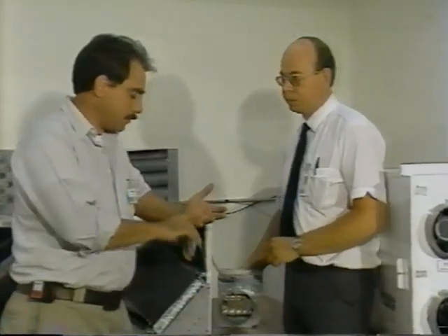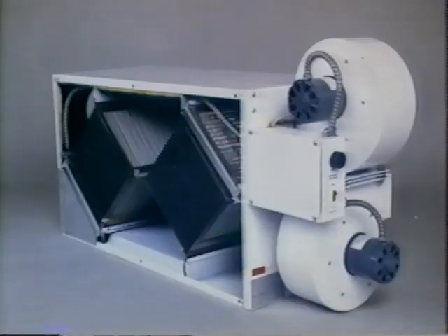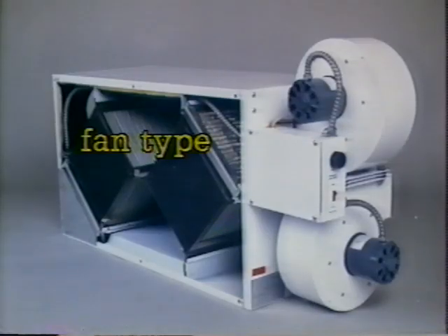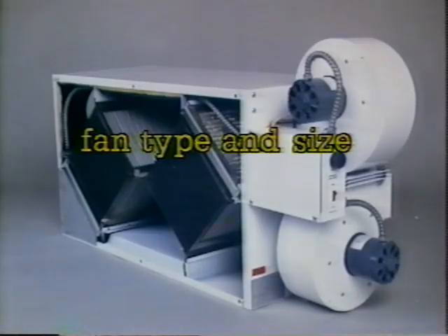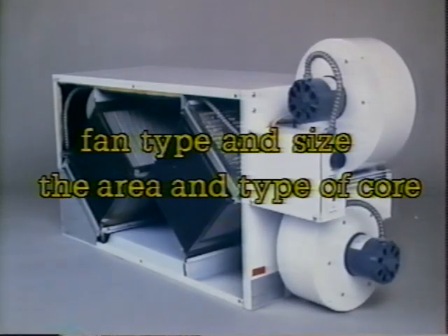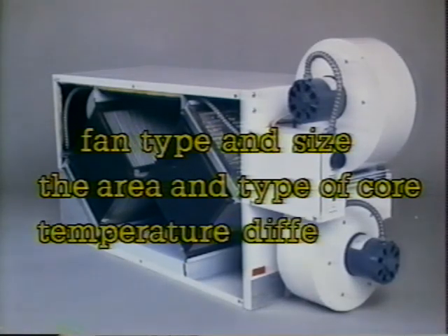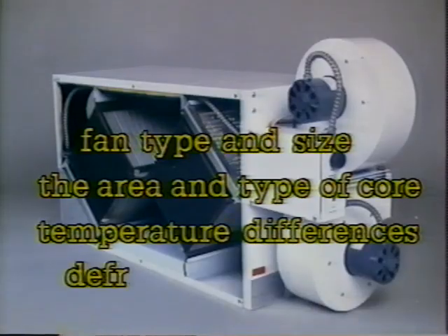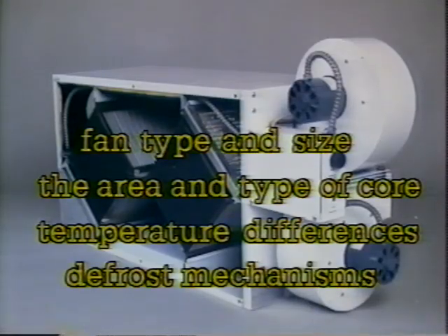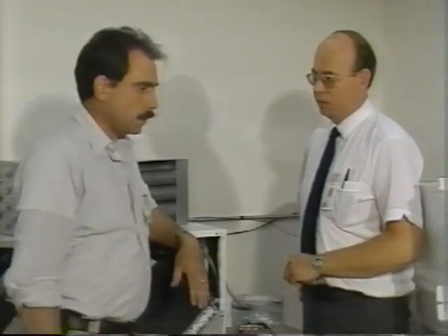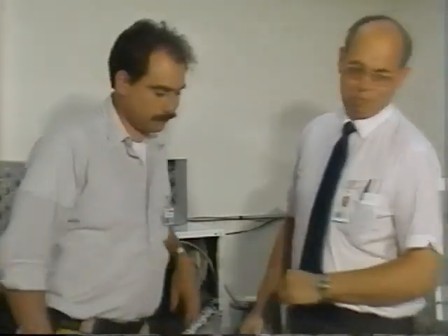Okay, let's see if I'm capable of summarizing this. The first issue is the size of fans to ensure that the system is balanced, and that obviously affects the performance of the unit. The second thing is that we have to make sure that we understand how large the core is and what configuration it has, and that affects the performance of the unit. The third item would be the temperature difference, and the fourth item is the defrost strategy. How'd I do? Pretty good. Let's go see how they're tested. Okay.